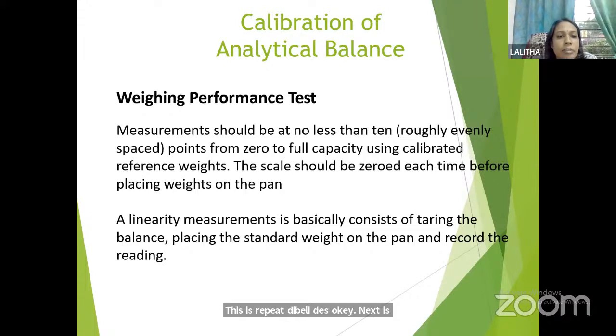Okay, next is calibration of analytical balance, the weighing performance test. Measurements should be at no less than 10, roughly evenly spaced, points from 0 to full capacity using calibrated reference weight. Normally, if we want to do a weighing performance test, we'll be using the calibrated reference weight given by the company. The scale should be zeroed each time before placing the weights on the pan. Linearity measurement basically consists of taring the balance, placing the standard weight on the pan and recording the reading.